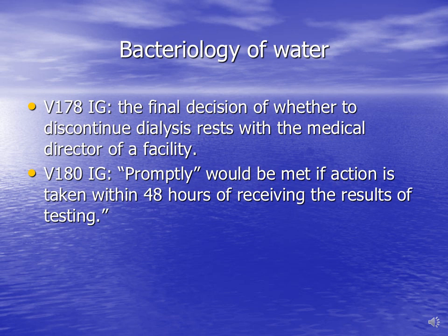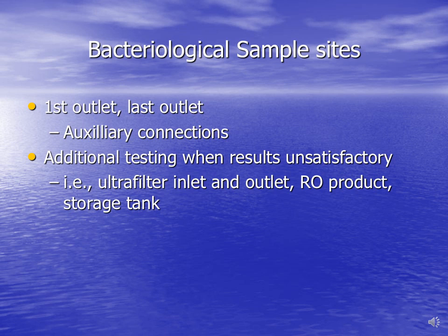Promptly would be met if action is taken within 48 hours of receiving the results of the testing. And these are the typical sites to be sampled: first outlet, last outlet, and auxiliary connections like the bicarb feed or bicarb mixing water, or if you have a granule system, the granule system. If you have a reuse system, the reuse system are auxiliary connections.